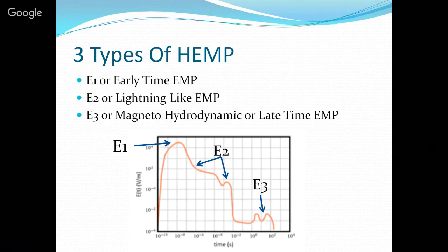The third type is an interesting one, E3 or late time EMP, caused by a different phenomenon called the magnetohydrodynamic EMP. It's easier to remember as E3 or late time. It causes a pulse very low in frequency, lasting seconds to tens or even hundreds of seconds, almost a DC-like signal. It occurs over a wide area and can have great effects on a power system, as we'll see.